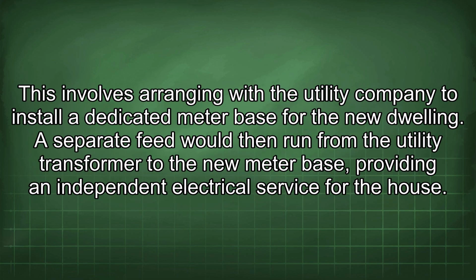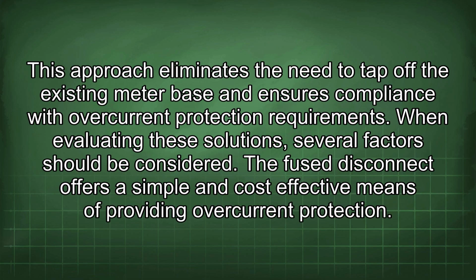This involves arranging with the utility company to install a dedicated meter base for the new dwelling. A separate feed would then run from the utility transformer to the new meter base, providing an independent electrical service for the house. This approach eliminates the need to tap off the existing meter base and ensures compliance with overcurrent protection requirements. When evaluating these solutions, several factors should be considered.